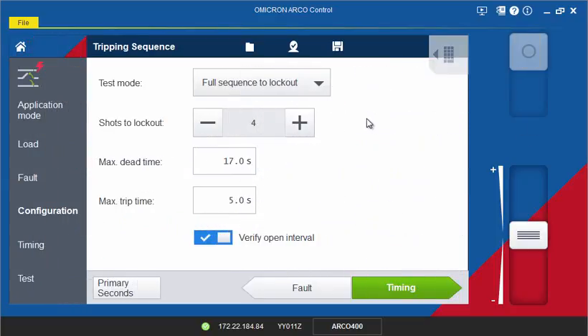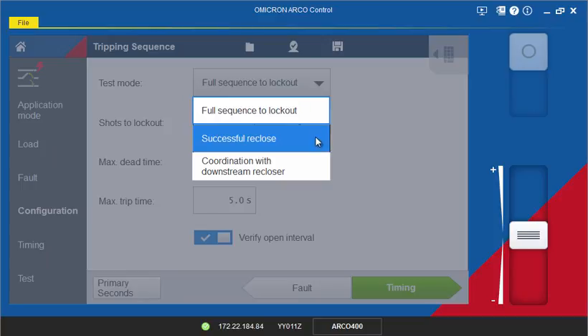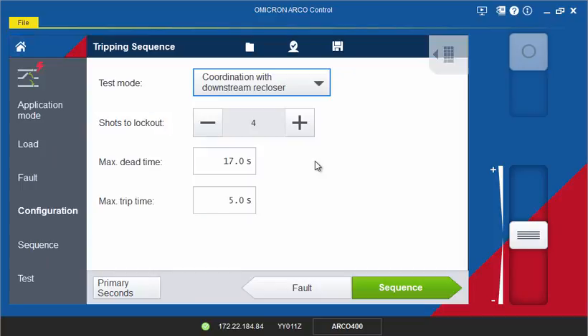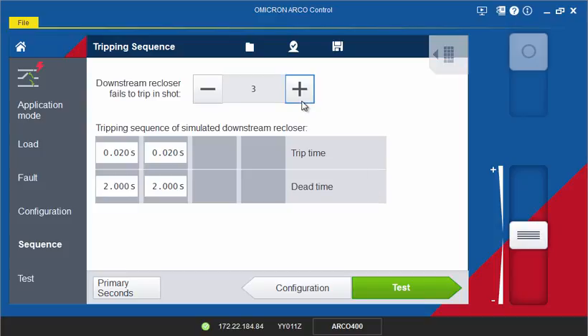The third test mode is used to test the sequence coordination feature of a recloser control. A downstream recloser is simulated by the software. Enter the shot after which the simulated recloser fails to trip together with its trip and open interval times in the table.